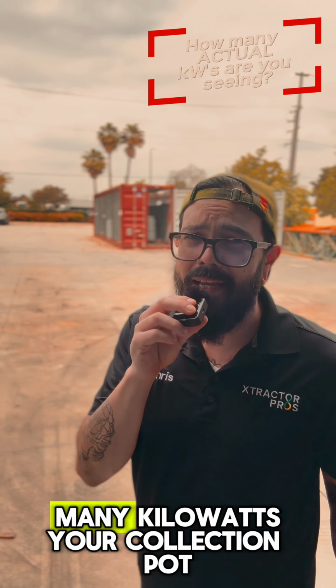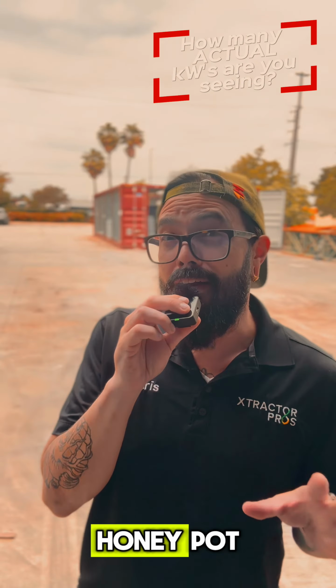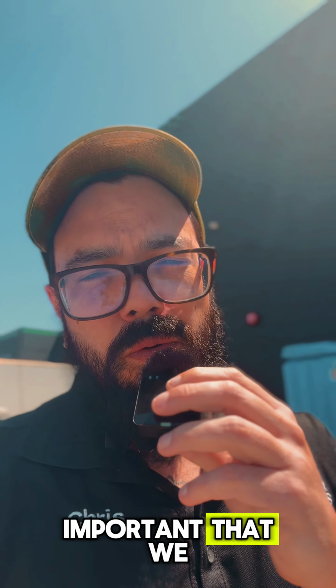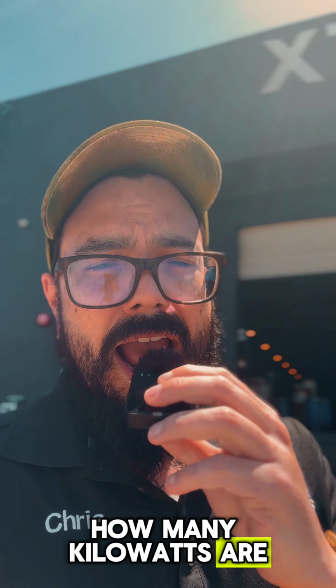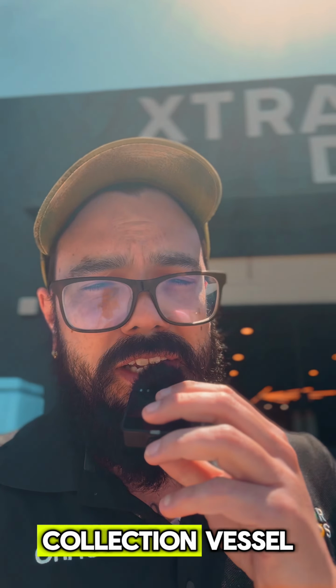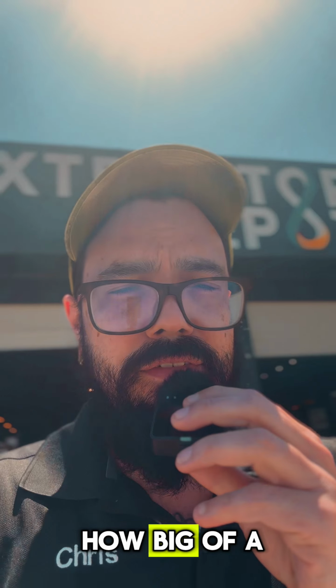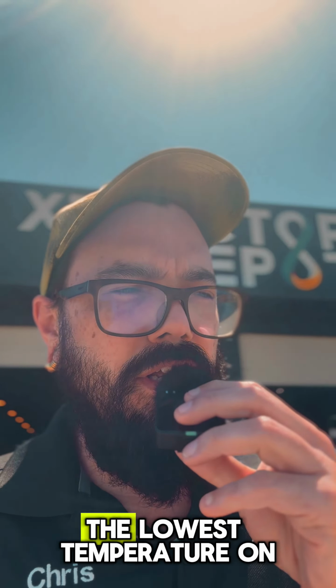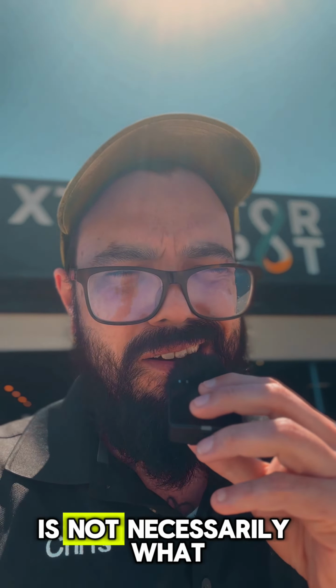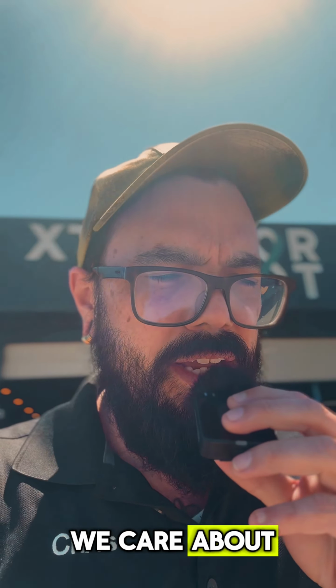Let's talk about how many kilowatts your collection pot, honey pot, your collection vessel is actually seeing. It's going to be important that we know how many kilowatts are actually being applied to our collection vessel so that we know how big of a chiller we actually need. The lowest temperature on a chiller is not necessarily what we care about. It's more so how much power the chiller has at the temps that we want it to be at.